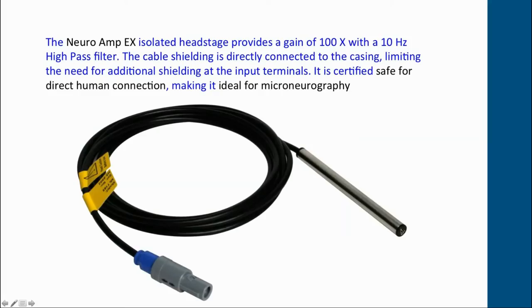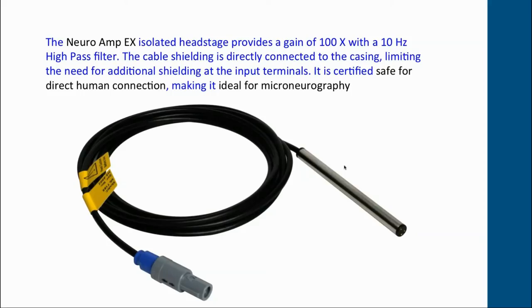If you use intraneural stimulation through the microelectrode, you can attach a small mini-alligator clip directly to the terminal of the active electrode and deliver currents up to 1 mA without fear of damaging the circuitry. The NeuroAmpEX is safe for direct human connection, making it ideal for microneurography. Its shape also allows it to be used for animal research — it can fit into a Narishige micromanipulator — making it ideal for extracellular recordings from individual neurons in the brain or from peripheral nerves in anaesthetised animals.